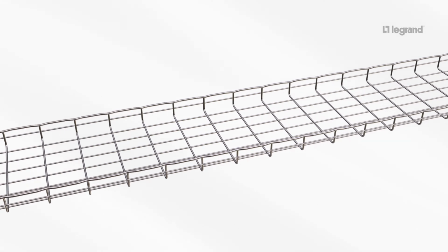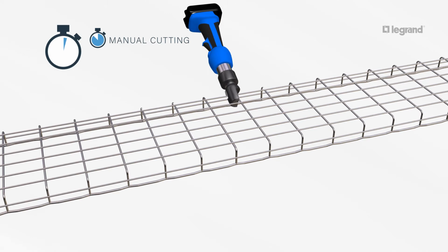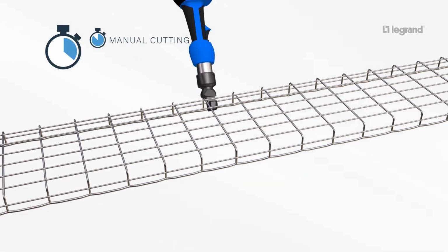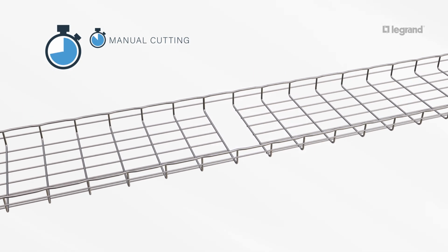on your next installation. Always begin cutting the bottom wires first, with the tray upside down. Rest the lower jaw against the crosswire. This will angle the cut away from the weld. A proper cut will not leave sharp edges. Cut the bottom wires, alternating side to side. Flip the tray over and cut the top wires.